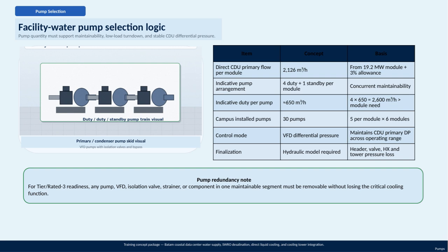Across the campus, this means 30 pumps in total, 5 pumps per module for 6 modules. We control these pumps using a variable frequency drive based on differential pressure, which keeps the CDU's primary differential pressure stable over the whole operating range. However, we still need to finalize these specifications using a detailed hydraulic model that captures pressure losses through headers, valves, heat exchangers, and cooling towers.